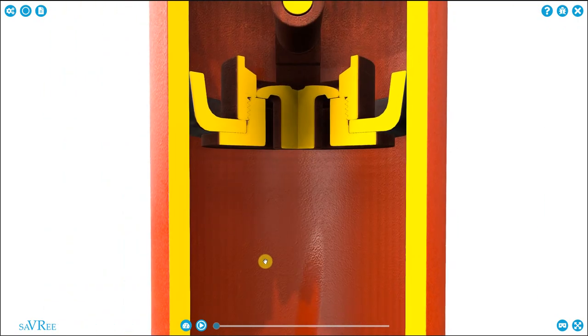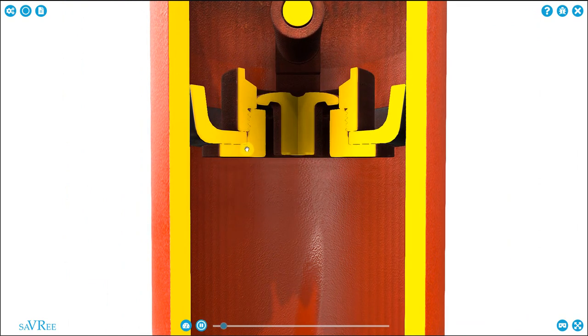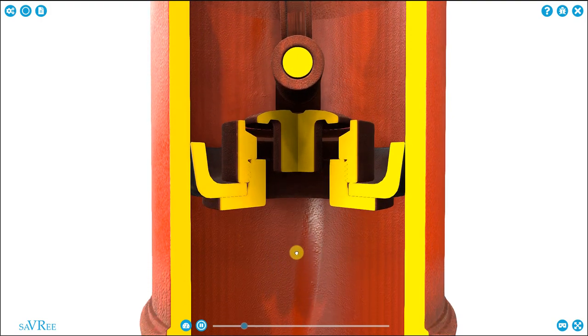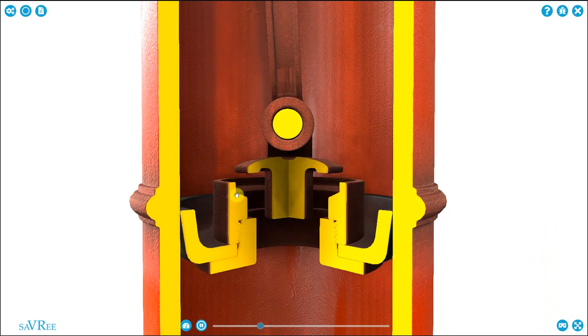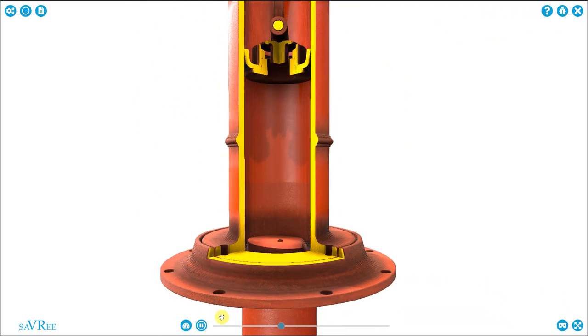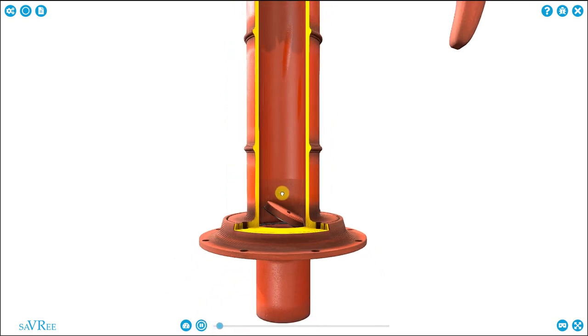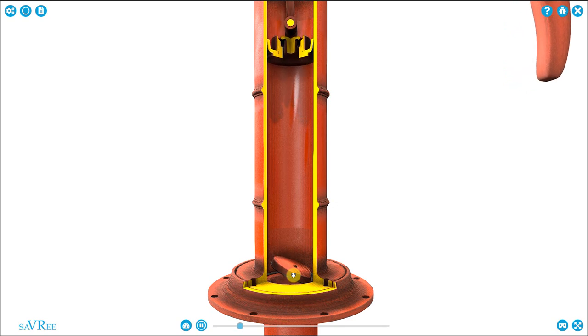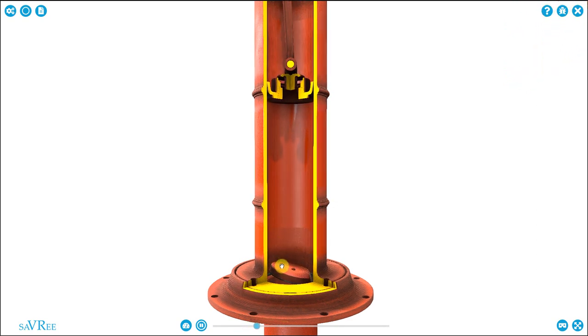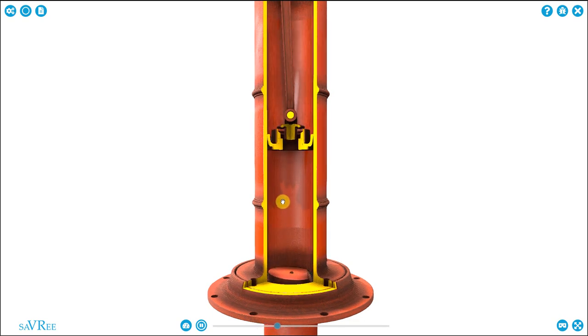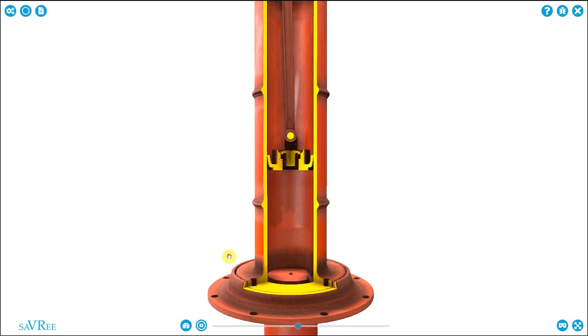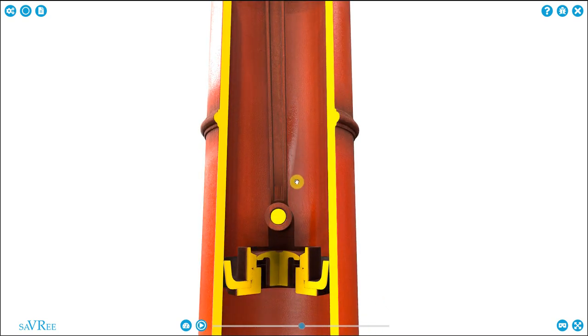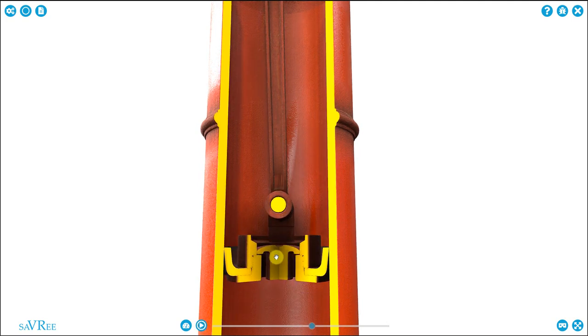Let's just press play. As the piston moves down, disc comes off the seat, the valve is opened and we get fluid flow from the bottom or the underside of the piston to the top side. At the same time, we are now closing the foot valve. Back it up. The piston is coming down. The foot valve is closing. The reason we close the foot valve is because the fluid in this space is then going to be compressed. And as it's compressed ever so slightly, it's going to just leak out and transfer to the other side of the piston. So we've now got the fluid on top of the piston.